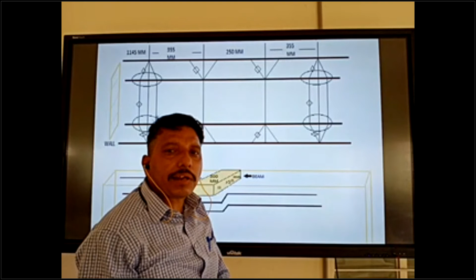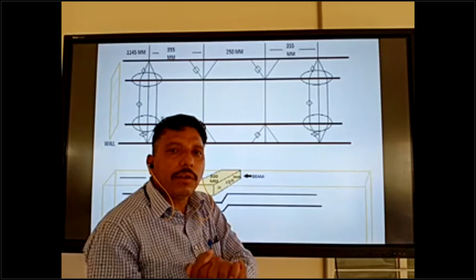And the cutting part value you can use is 40 mm, same like that. In a bridge, the cutting part always comes on the height side, offset, height side coming. Only horizontal 90, base side coming. If you are making a horizontal 90, the cutting part comes on the base side, you multiply by the base side. But for bridge offset, inner or outer 90, vertical 90, the cutting part comes outside.